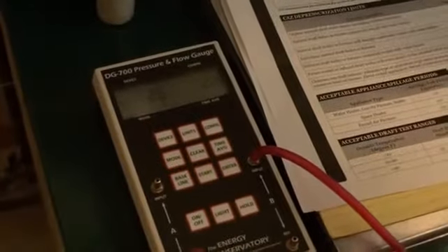Again, we want to have at least -0.75 pascals, and in this case both appliances are running and we have -2 pascals, and as it heats up, the draft starts to pick up a little more and more. So basically we've established draft and we can continue with our diagnostics at this point.